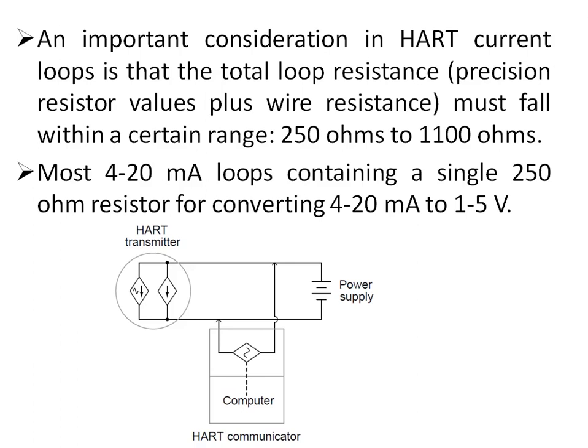One important consideration for HART is that the total loop resistance must be in the range of 250 ohms to 1100 ohms. This 250 ohm minimum is easily met by placing the precision resistor used for converting 4 to 20 milliampere to 1 to 5 volts. In the next video, I will discuss HART communication basics further and why this 250 to 1100 ohm limitation is required. This is the HART transmitter block diagram, which can also be connected to a HART communicator for troubleshooting or calibration purposes. Thank you for watching.